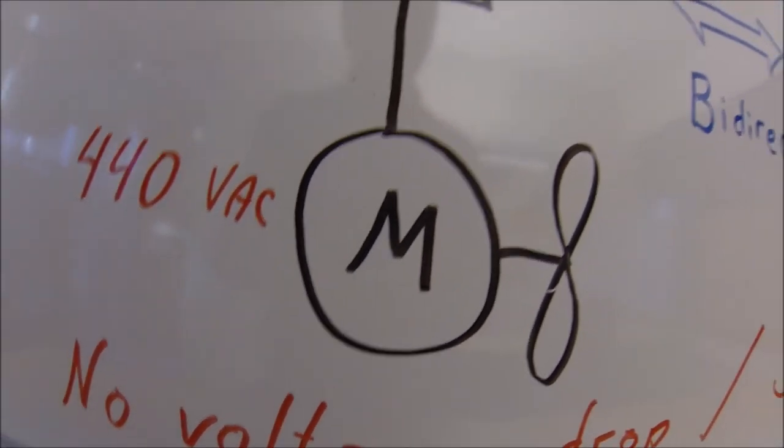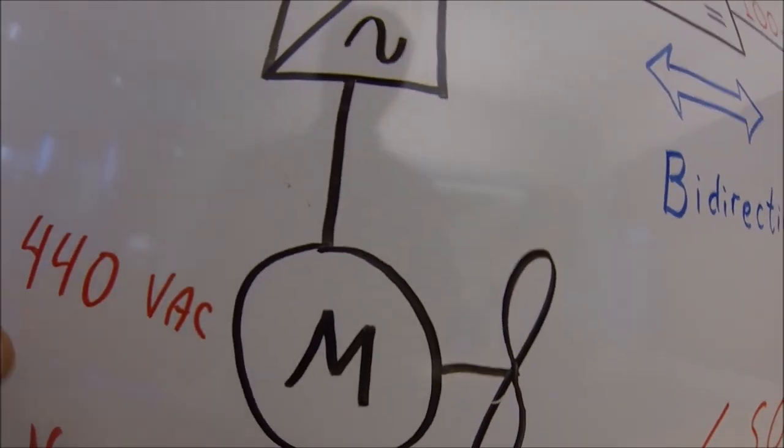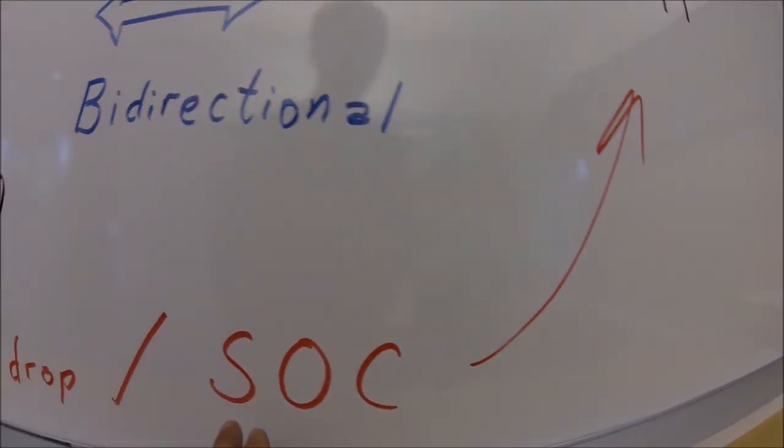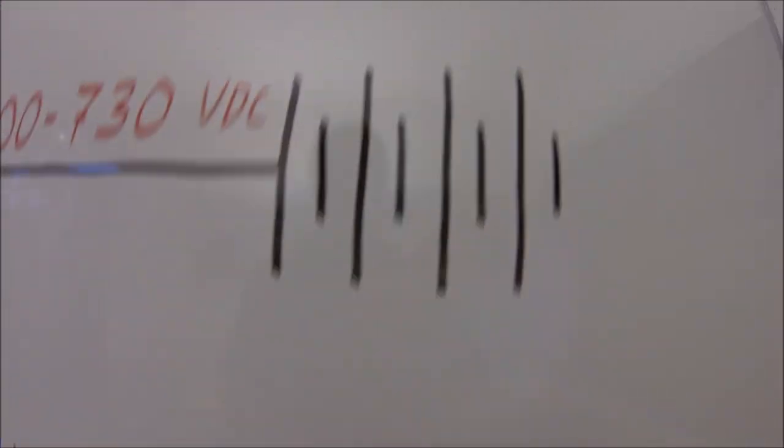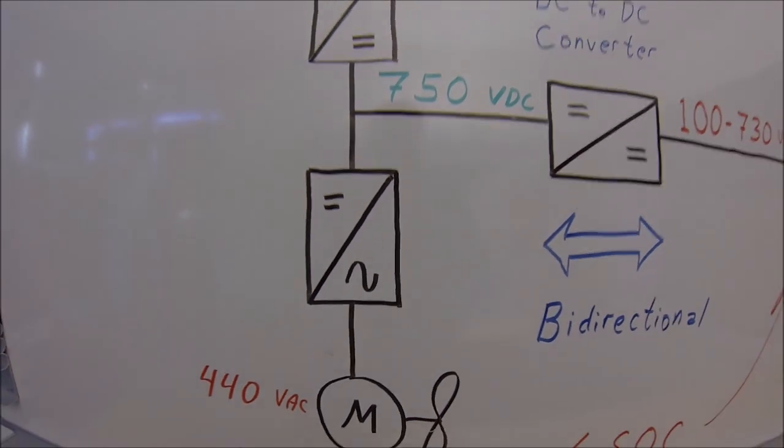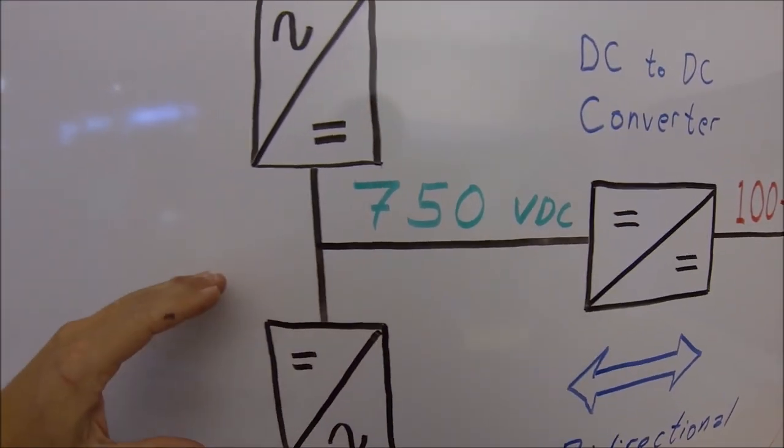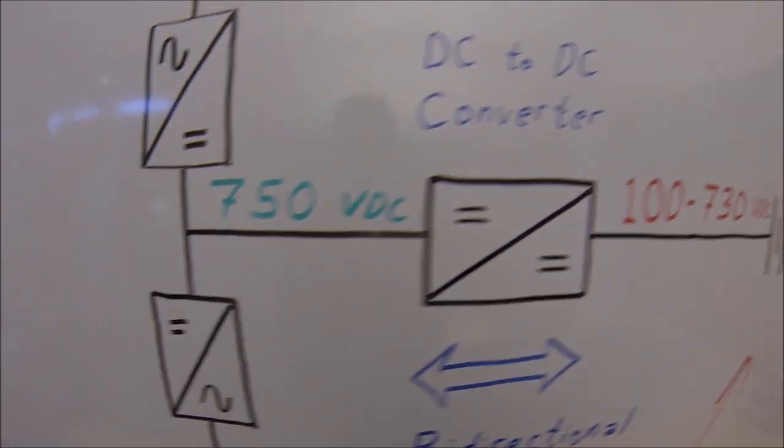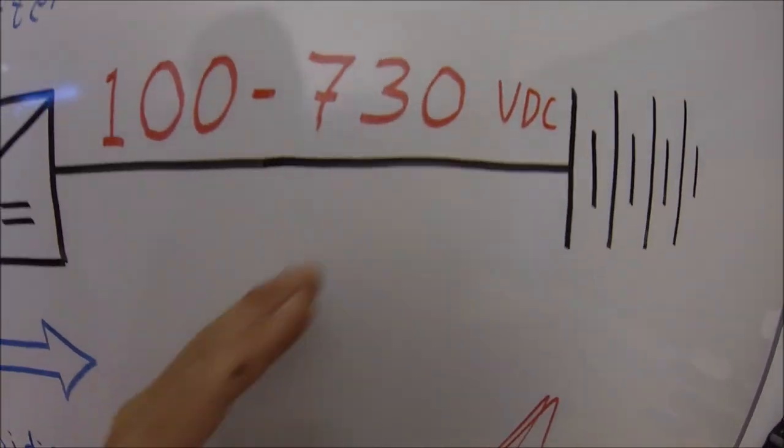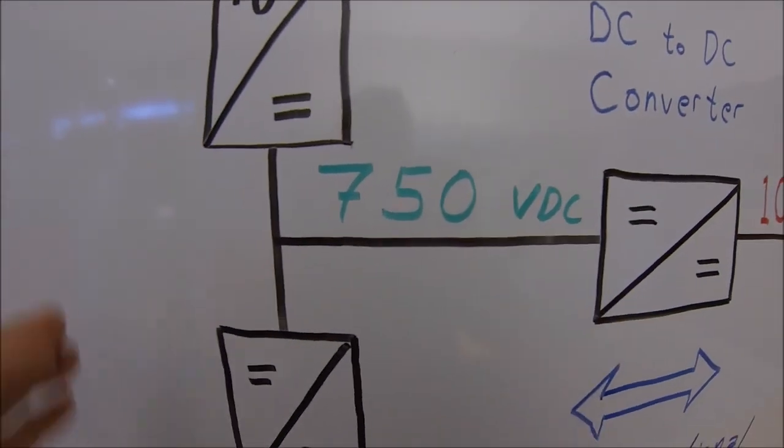Motors for ship propellers and heavy consumers are quite dependent on the maximum highest voltage and the voltage drop as a function of state of charge will then not be seen on the consumers. However, be aware that to keep a constant kilowatt on your consumer side when the voltage drops off on the energy source, of course the amperes have to go up to supply the same kilowatt.